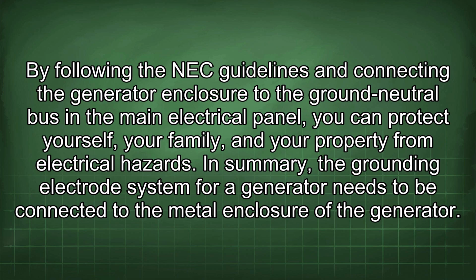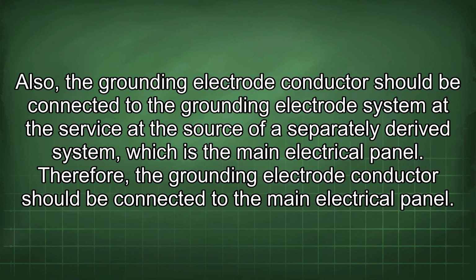In summary, the grounding electrode system for a generator needs to be connected to the metal enclosure of the generator. Also, the grounding electrode conductor should be connected to the grounding electrode system at the service, at the source of a separately derived system, which is the main electrical panel. Therefore, the grounding electrode conductor should be connected to the main electrical panel.